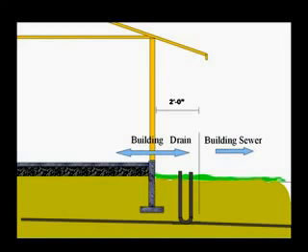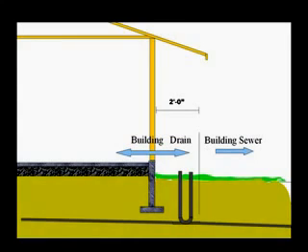Drain sizing is accomplished by determining the fixture unit to be drained for each fixture by using the drainage fixture unit values table 7-3. You will need to know if the project you are sizing is a private residence, a public building or a building used for assembly so that you can use the proper column in table 7-3 to get the fixture unit values. After determining the building type, you will need to know the specific type of individual fixtures and the required fixture units from the correct building type column. Then total the fixtures that will be served by each section of the building drain.